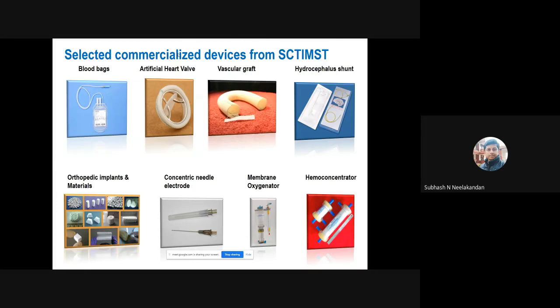Coming to Chitra back again, these are some of the products which were developed, tested, and commercialized by Sri Chitra. If you look at these devices like blood bags, artificial heart valve, vascular graft, or any orthopedic material, none of these will be following a similar pattern or similar experiments at the functional level, because depending upon the user requirement, we need to develop a testing protocol. So the testing protocol for a blood bag will be entirely different from an artificial heart valve, which will be entirely different from a vascular graft.